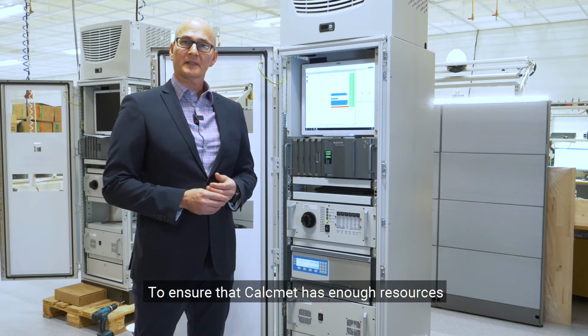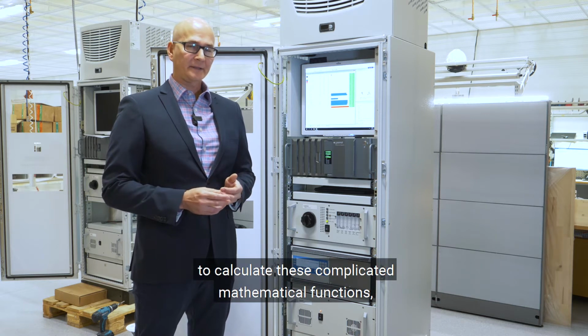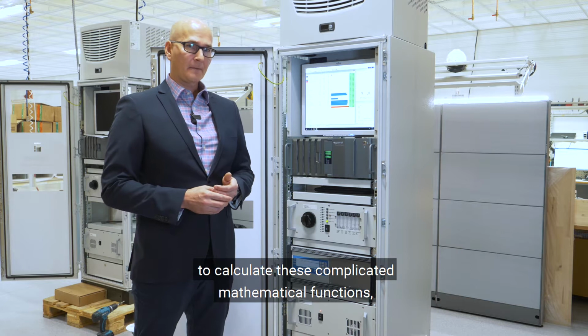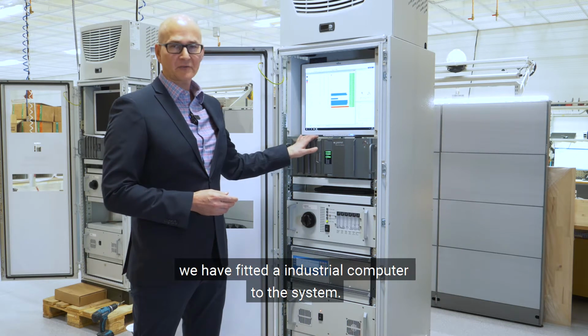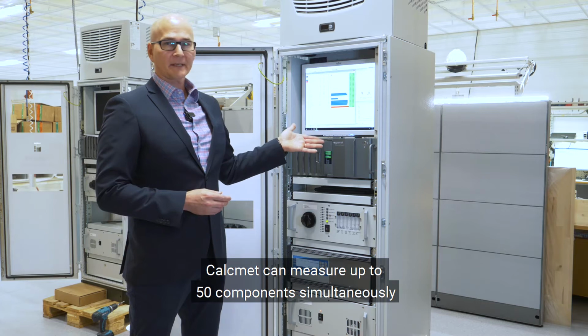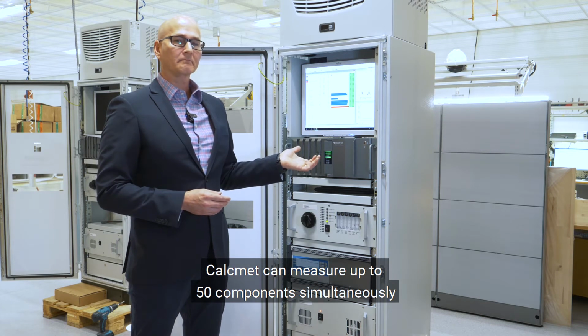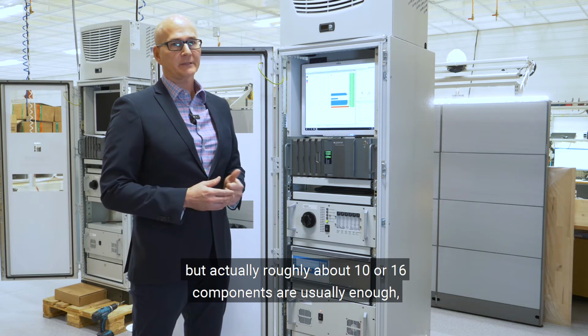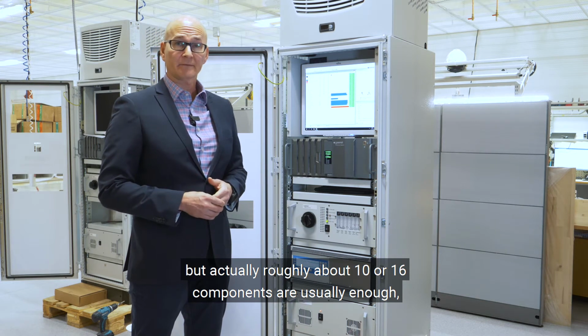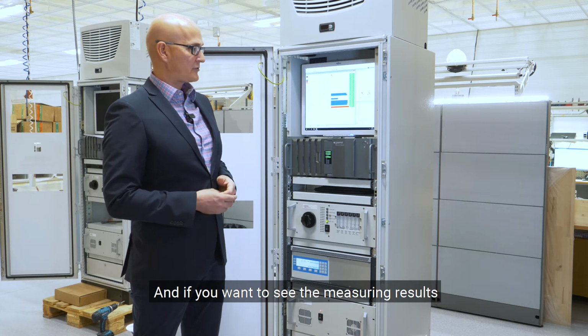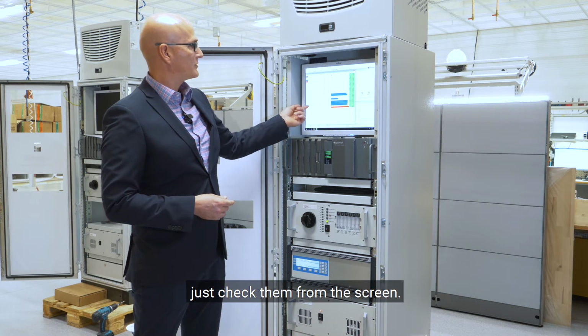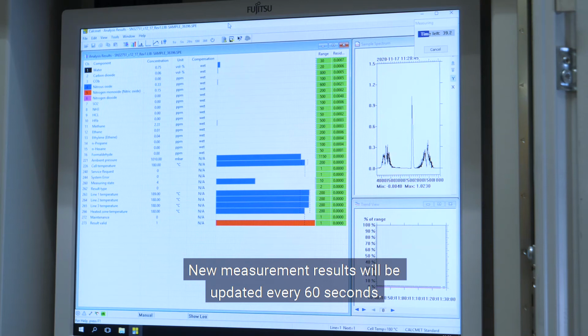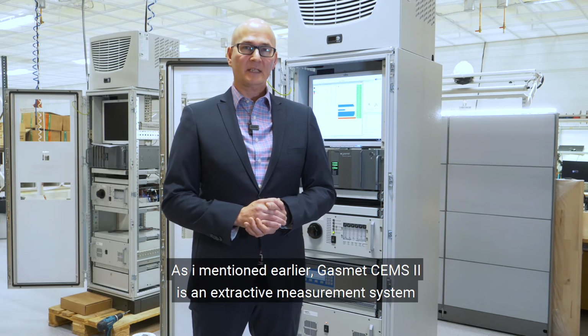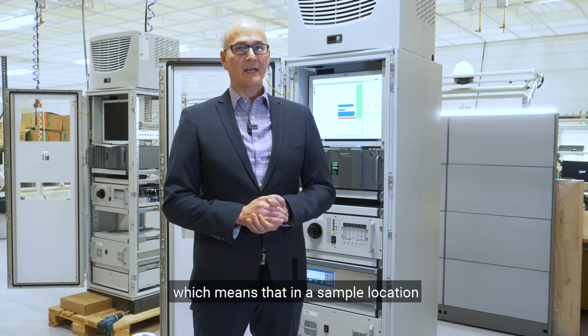To ensure that Gasmet has enough resources to calculate these complicated mathematical functions, we have fitted an industrial computer to the system. Gasmet can measure up to 50 components simultaneously, but actually roughly about 10 or 16 components are usually enough. And if you want to see the measuring results, just check them from the screen. New measurement results will be updated every 60 seconds.